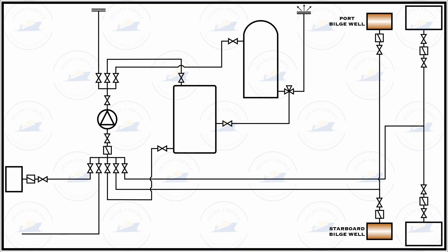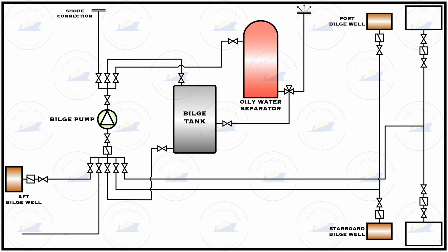Now let us shift our attention towards the bilge line. The bilge line in its simplest form has two typical bilge wells on the forward side of the vessel and one larger bilge well on the aft side. Taking suction from these bilge wells — either aft or forward — through the dedicated valve and filter assembly at the mouth of the bilge well, water from the bilges goes into the bilge pump. The bilge pump has a suction and discharge valve and a small filter at its suction. The discharge line goes to different elements: the shore connection for shore discharge, the bilge tank, and the oily water separator.